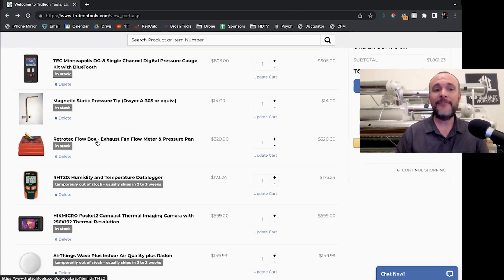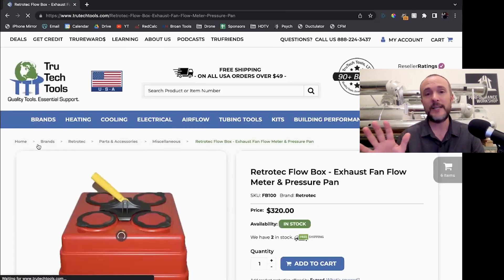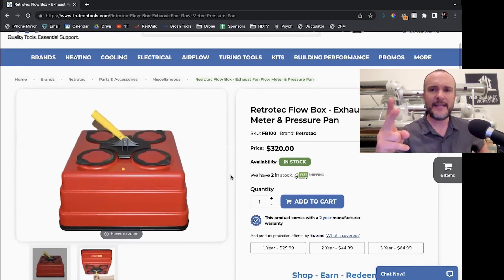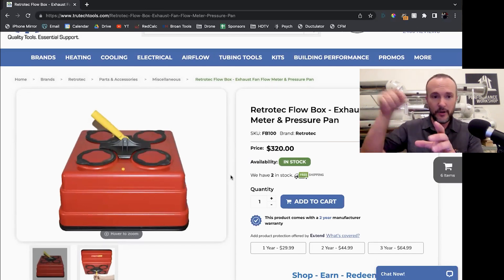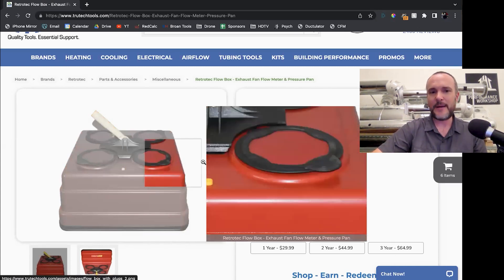Next thing in line is a Retrotec Flow Box. This is one box that can do two very useful things, and it's $320. It is a pressure pan — just a box that's completely sealed up that you hook a pressure probe to. That's the little yellow thing you can see right there, a pressure tap inside the box, so that you can put it over things that don't have a door and do a zonal pressure test on them.